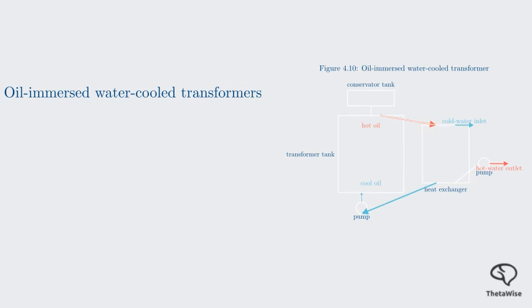exchanger. In a heat exchanger, the hot oil and cold water flow on separate, isolated paths, but in close proximity. The heat is transferred from the hot oil to the cold water. The newly cooled oil is then pumped back into the bottom of the transformer tank. At the same time, cold water from an external source, like a cooling tower, is pumped into the heat exchanger. It absorbs the heat from the oil and leaves the exchanger as hot water, which is then sent back for cooling.